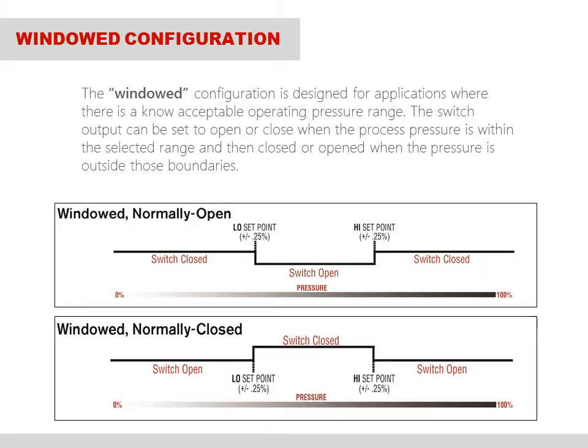For example, the window could be set for an acceptable operating range of 50 psi to 150 psi. That is to say, the low set point is 50 psi and the high set point is 150 psi. The switch will be closed or on when the pressure being monitored is between 50 and 150 psi. If the pressure goes below 50 psi or above 150 psi, the switch will open or turn off.